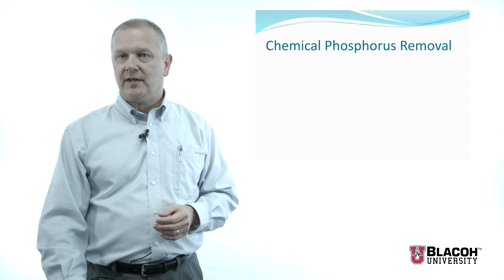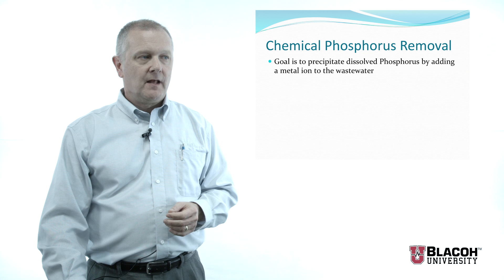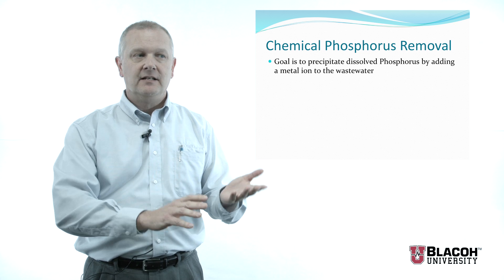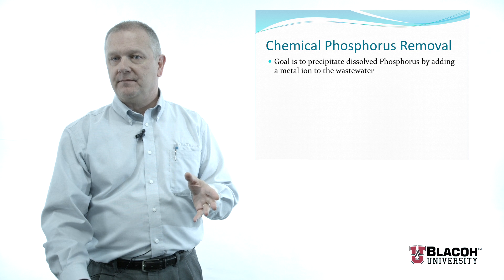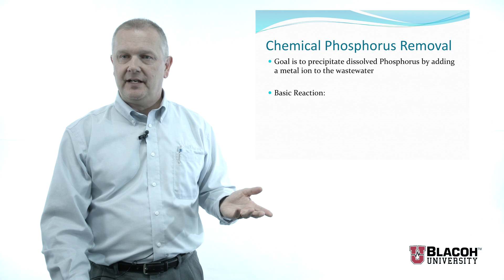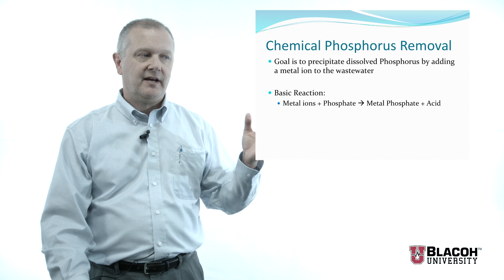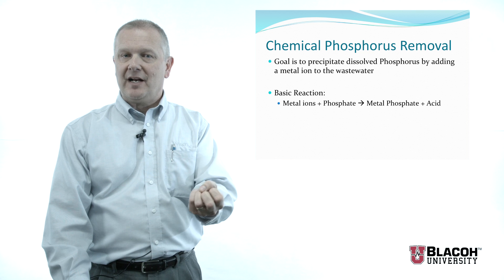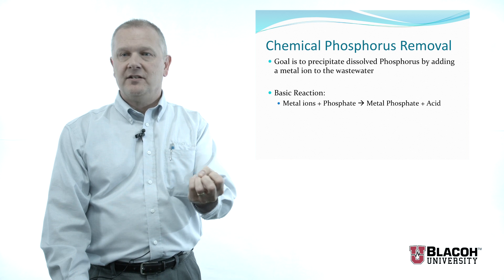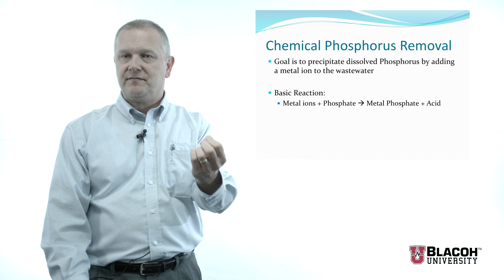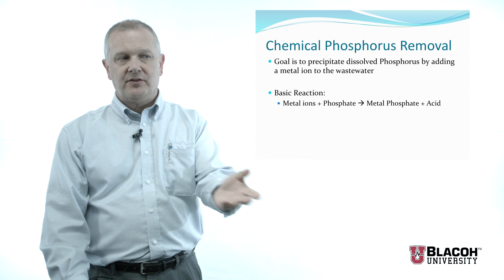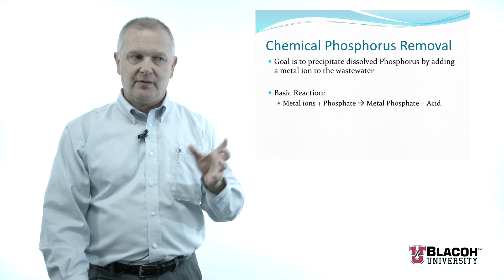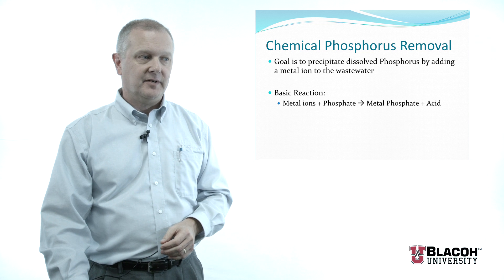Let's talk about chemical phosphorus removal first. The goal is to precipitate the dissolved phosphorus by adding a metal ion to the wastewater. Basically, the metal ions plus the phosphate dissolved in the water combine to form a metal phosphate that is insoluble and will precipitate as a fine solid, with an acid that comes out as a byproduct. Not enough to make the water very acidic, but it's something we calculate and think about when we design these systems.